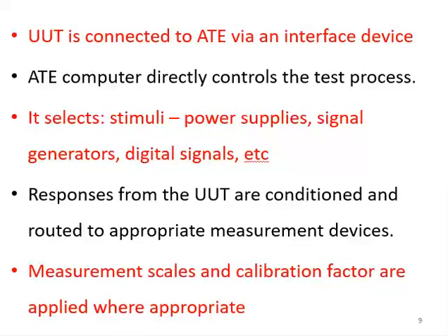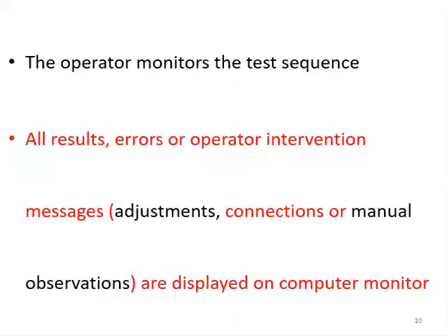The responses — signals detected from the unit under test — are conditioned and routed to the appropriate measurement device. The ATE can measure current, voltage, frequency, distortion, and many things. When a signal is detected from the unit under test, it is directed to the proper measurement segment. The operator monitors the test sequence, checks the display for results, checks for errors, and makes any needed adjustments.